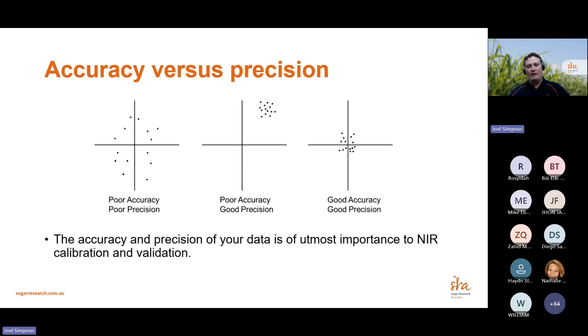So how do you bridge these two? How do you get NIR to move into the center? That's a process called validation. Basically, when you're predicting with NIR, you want about 10% of validation data if you can, where you've got the laboratory and the scan results. You do that to see what the distance is between these two, and then you correct for that, and that brings it in line.